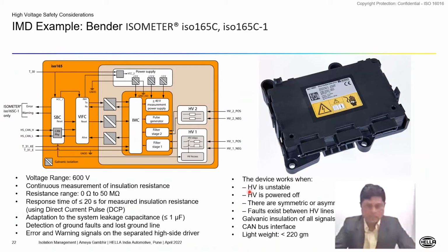This device will work when HV is not stable, and when HV is powered off. It can measure symmetric as well as asymmetric insulation faults. During measurement, it provides galvanic insulation, so because of its internal design, it won't introduce an isolation fault in the vehicle that previously didn't exist. It also has a CAN bus interface so it can easily interface with other vehicle subsystems.